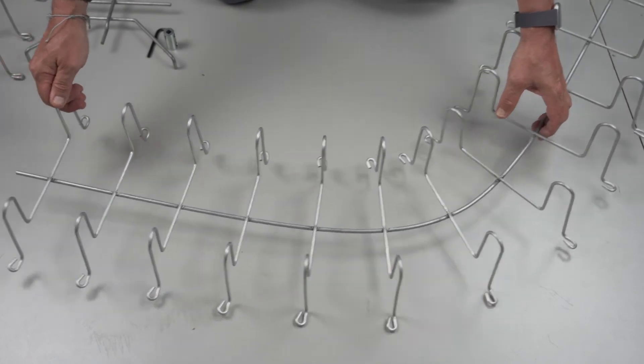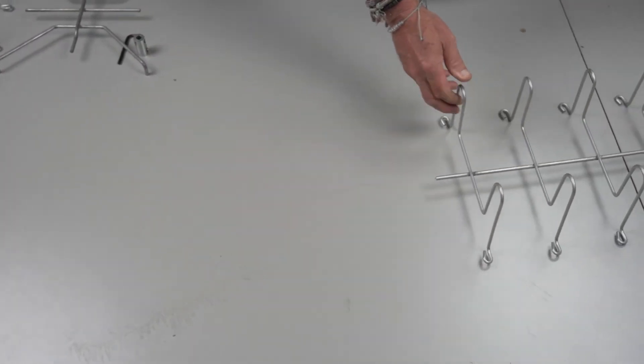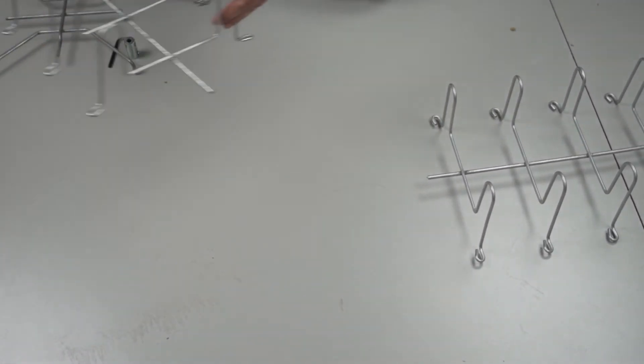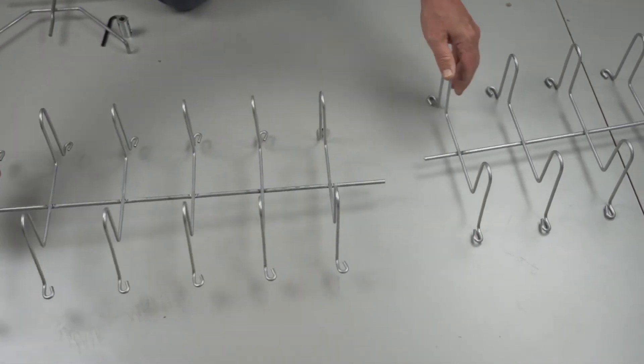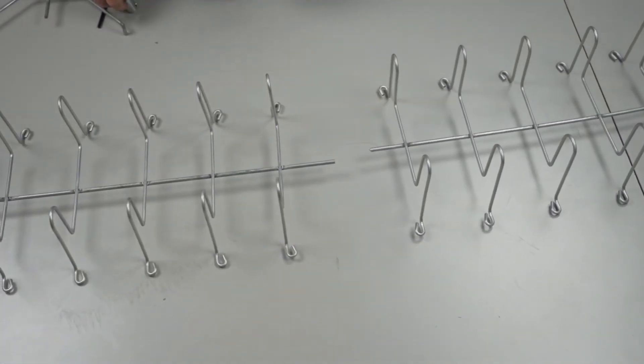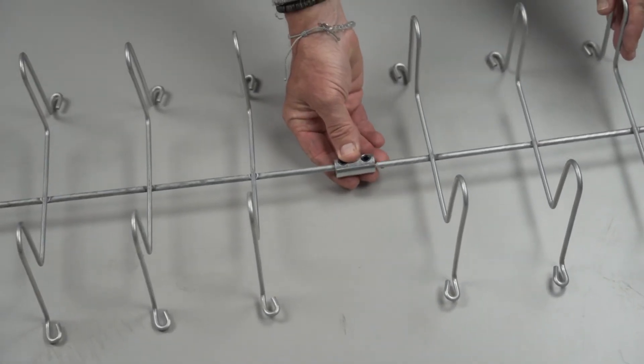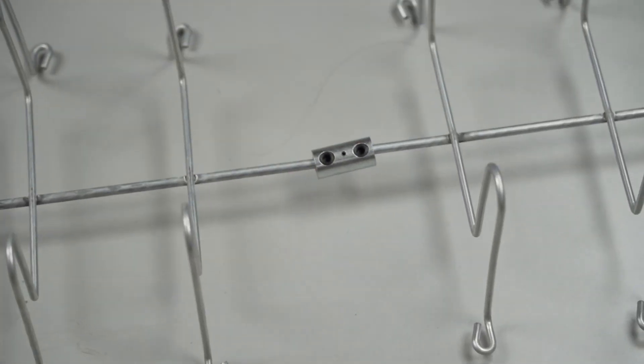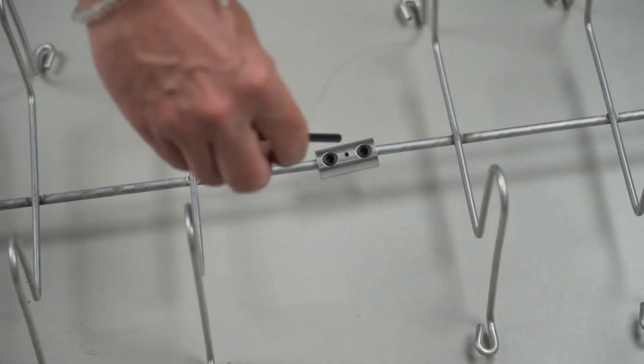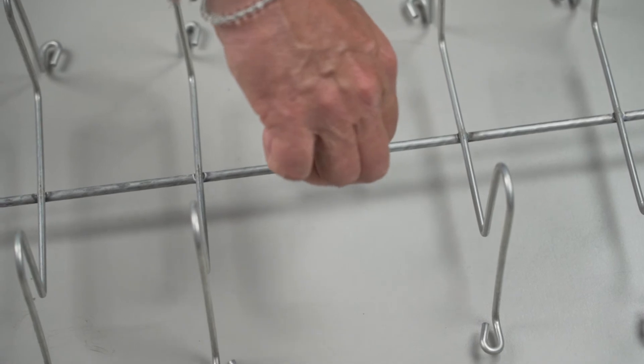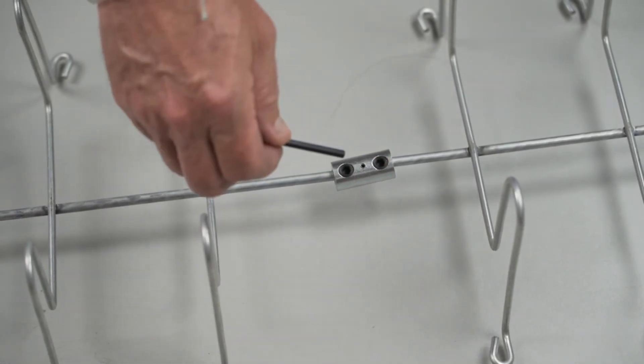When we join two sections of tray together we have an integral part that's called a CB12 and it's simply a barrel bolt that we'll install between the two sections. We'll then take an Allen set screw and tighten that up to make a bonded connection as well as our mechanical connection.